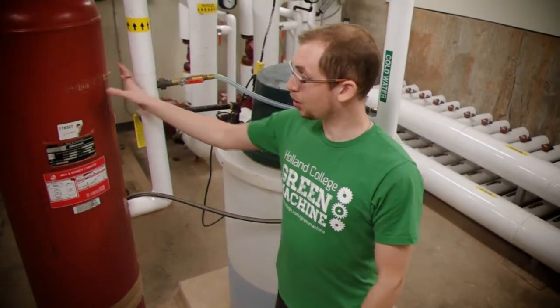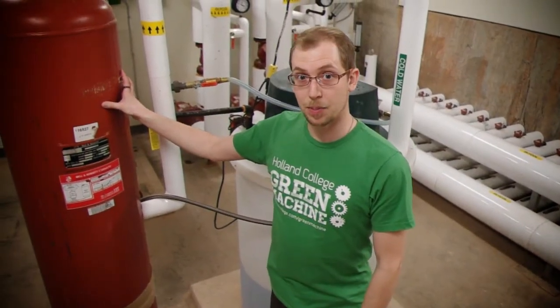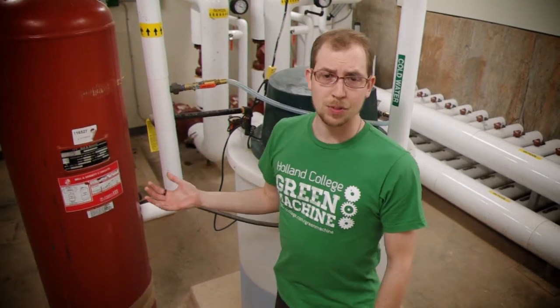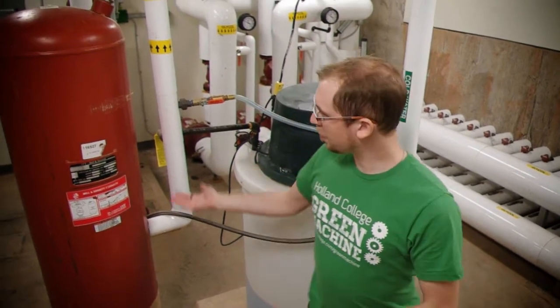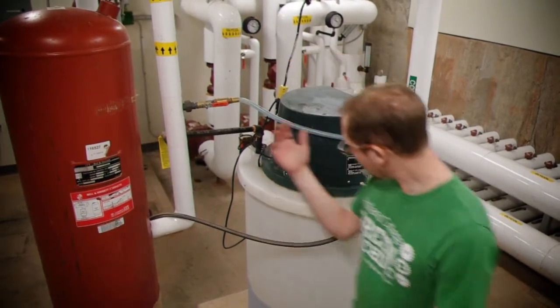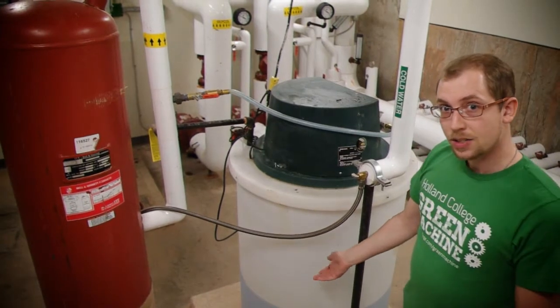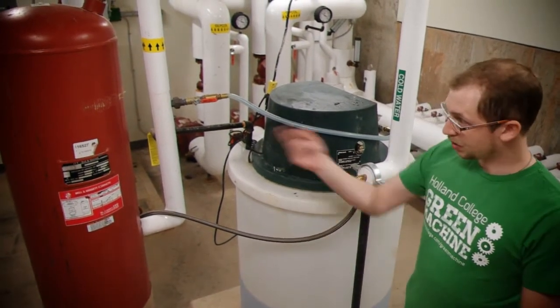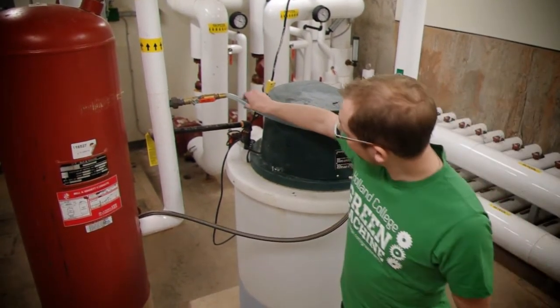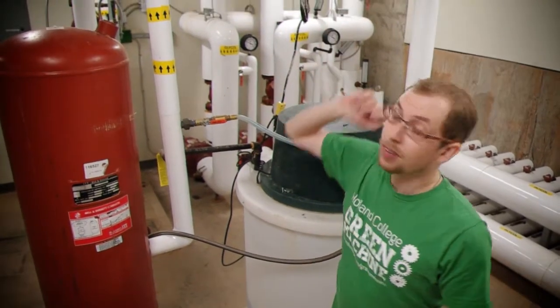So what we have here is the thermal expansion tank for the ground source heat pump system. In the event that there might be some sort of thermal expansion that occurs because of the fluctuating temperatures either from the building or underground, then this will compensate for anything that gets blown off. What we have here is the refill for that. So let's say that they need to refill it because that blew off. You can grab the liquid right from here in the glycol can, go back and follow that pipe, and go right back into the system again.